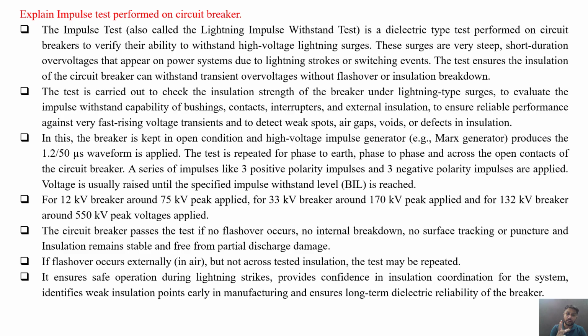It provides confidence in insulation coordination for the system, identifies weak insulation points early in the manufacturing stage, and ensures the long-term dielectric reliability of the circuit breaker. So this is all about the impulse test performed on the circuit breaker.